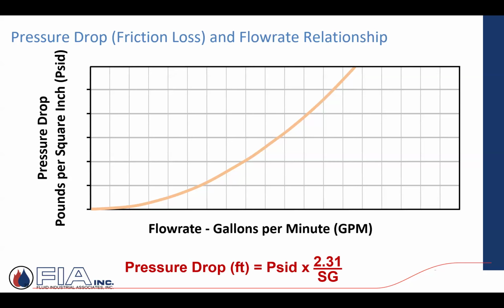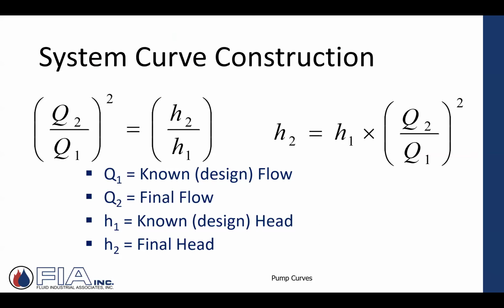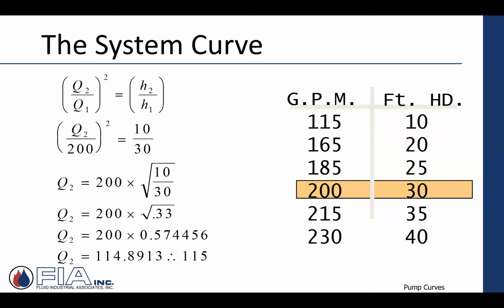There is a relationship. So the system curve is based on that formula, if you will: I have a design flow rate and a design head loss. I want to increase or decrease that flow. Square that answer times my original and it becomes my new head loss. And so they're going through this exercise, and it's just building a system curve. They say, I've got a design condition of 200 gallons a minute and a corresponding pressure drop of 30 feet. If I want to build a system curve, what I can do is arbitrarily pick other pressure drops and figure out the new flow rate, or arbitrarily pick other flow rates and establish the new pressure drop.